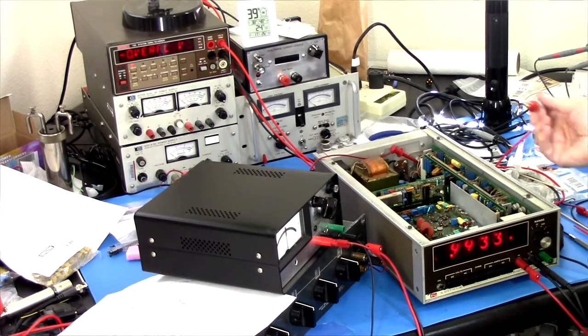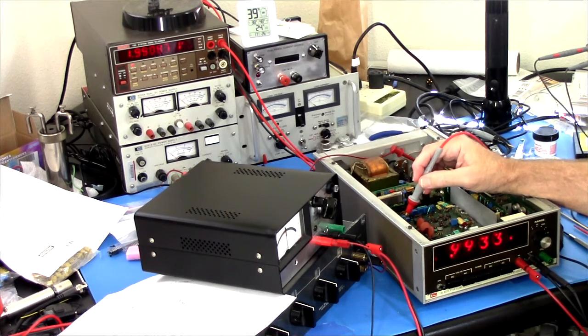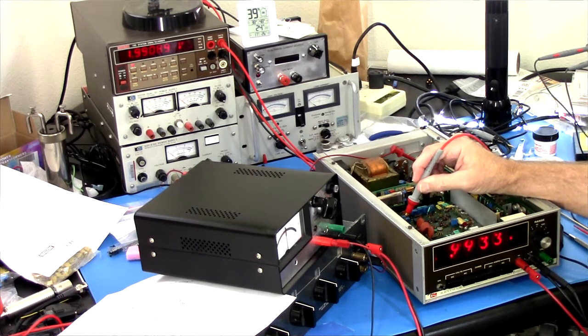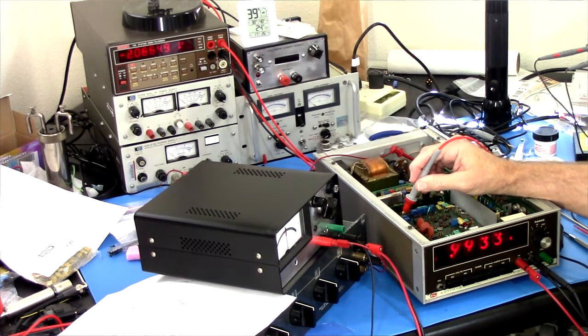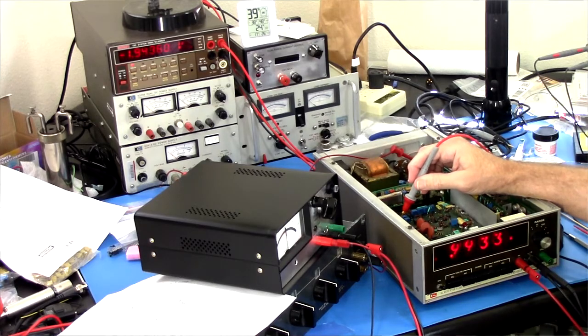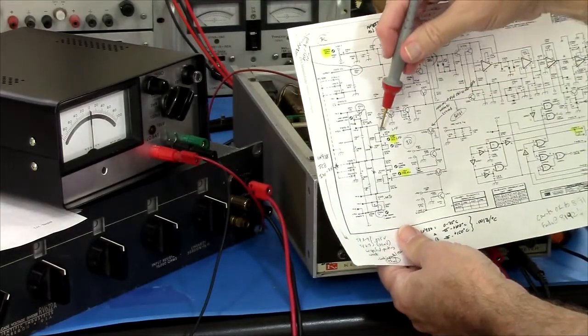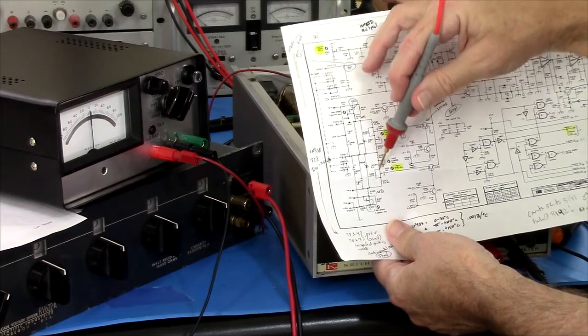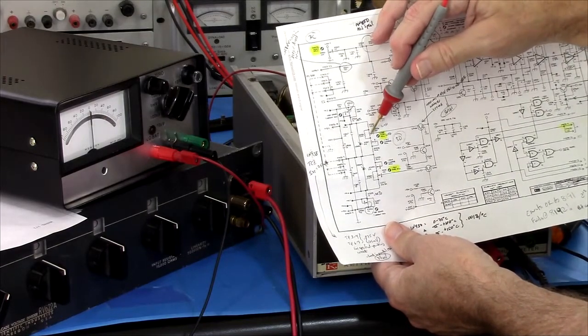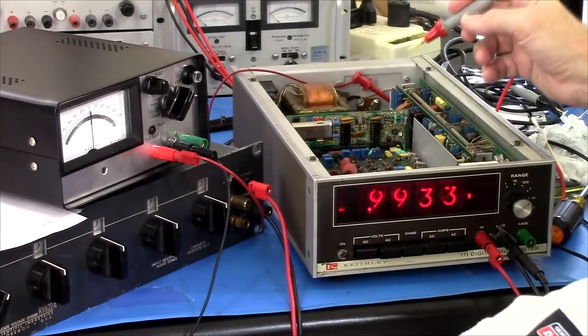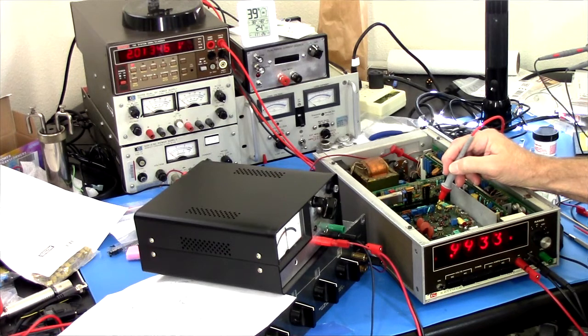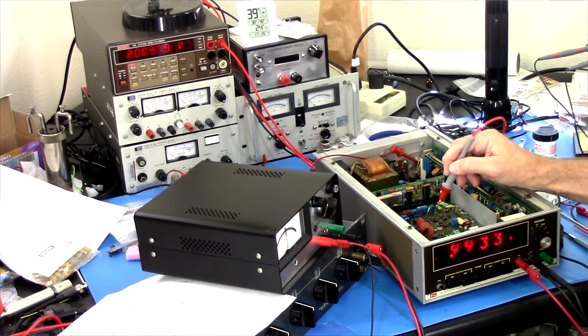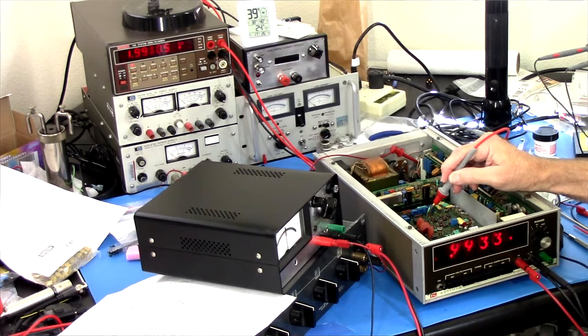And one thing, okay, so what we can do is we can look at the voltage, the calibration voltage, the output. What I'm looking at is the high and low side of that potentiometer. And this is calibrated, should be calibrated to exactly two volts. So if I go there, that's one side. This is on the one that has the problem. 2.01. I don't know why it's bouncing like that. And here, 1.99. You can see that two volts is in the middle of those two.